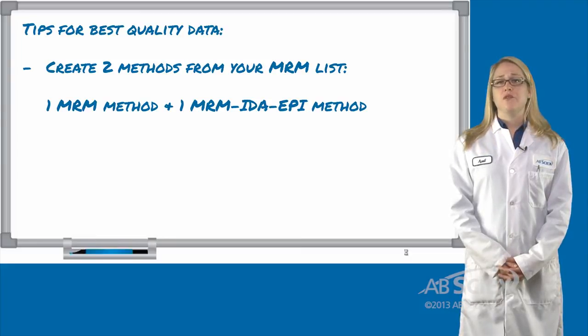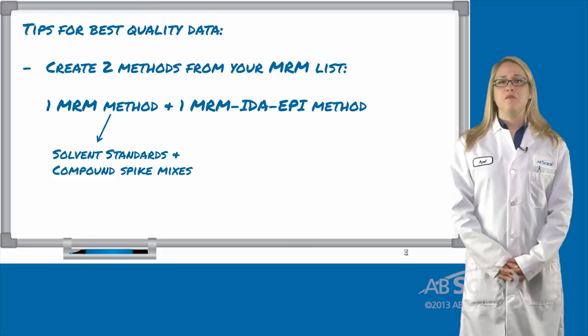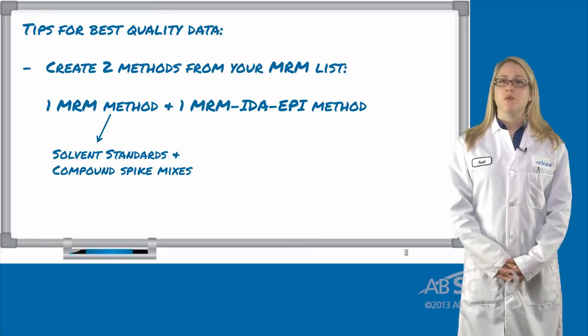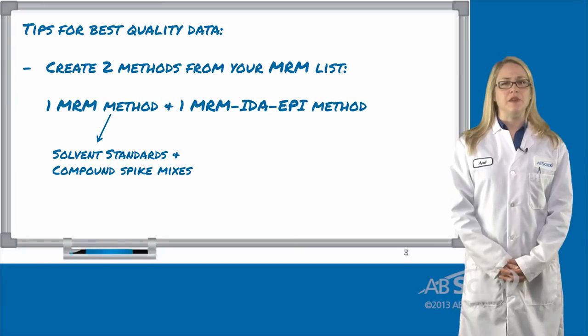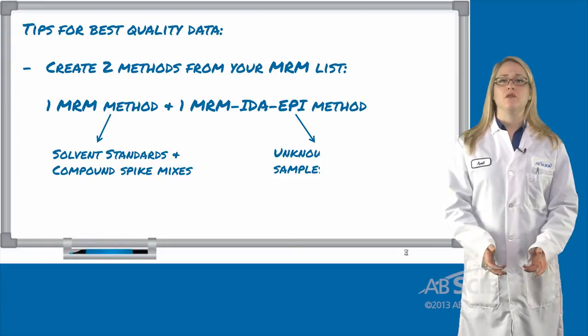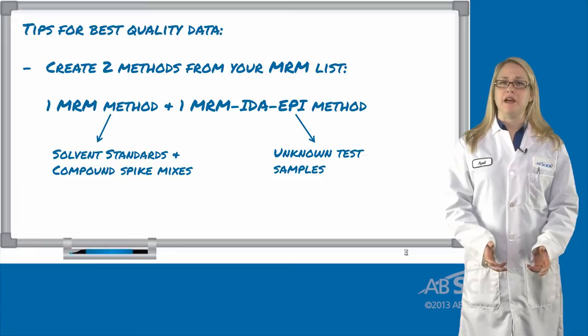We suggest you run your mixes that contain your target compounds, like standards or matrix spike samples, with your standard MRM acquisition method, no IDA EPI triggers, and run your unknown samples using the MRM IDA EPI method.